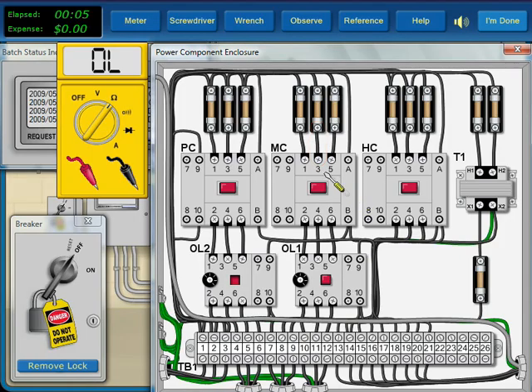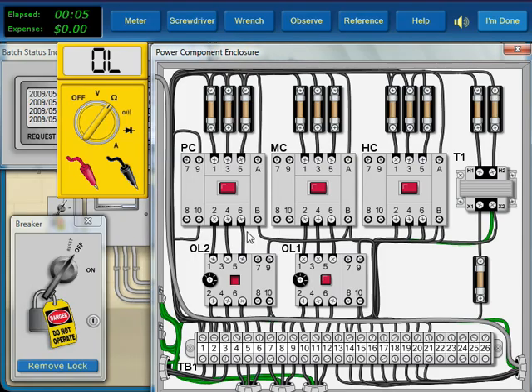We begin to disconnect the wire, but find a loose terminal. Since this fits the symptoms, we tighten the terminal to repair the circuit.